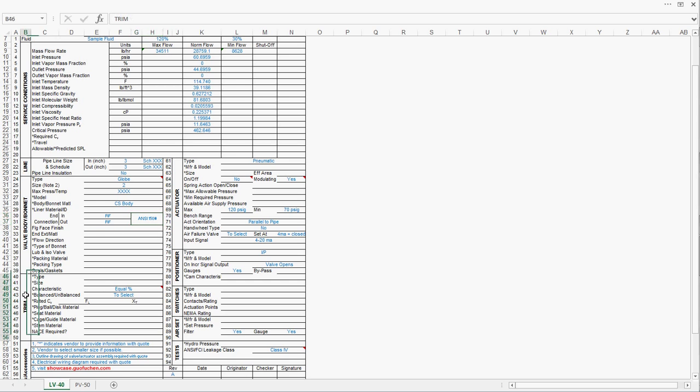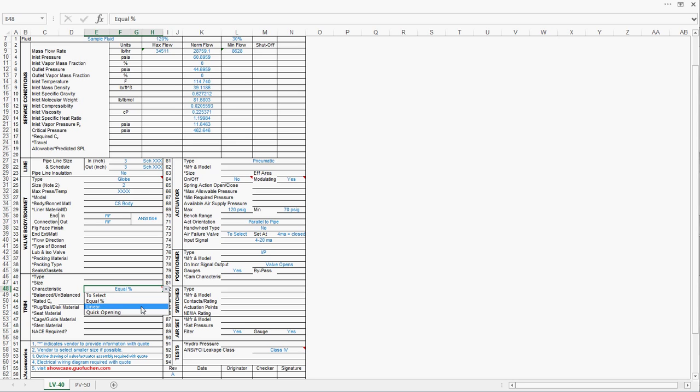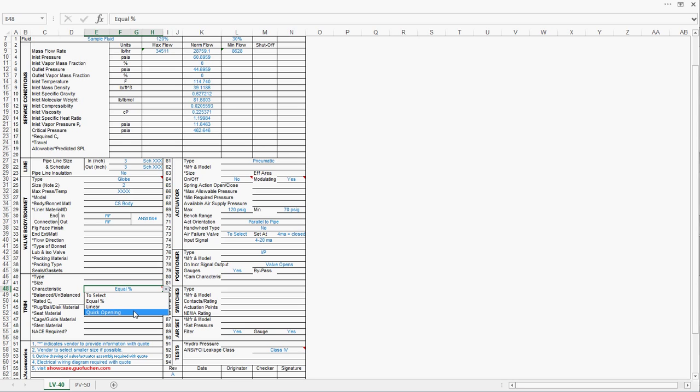Now, let's move to the trim. Regarding the valve characteristics, there are generally three kinds: Equal percentage, linear, and quick opening. Equal percentage is good for most of the cases, while linear is primarily for liquid level control valve. Quick opening are primarily for on-off valves. Since we are talking about liquid level control, we are going to choose linear.